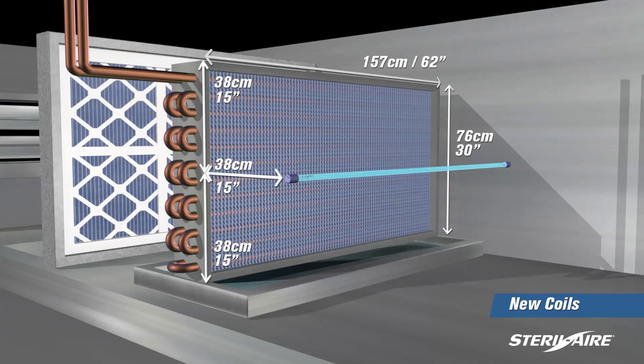To maintain a minimum UVC dose on a new coil and to keep the coil clean, we recommend using one horizontal row of Steril-Aire across the full coil face for every 30 inches, 76 centimeters of vertical coil height.